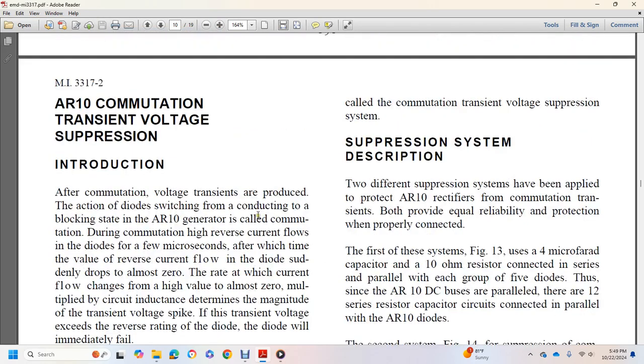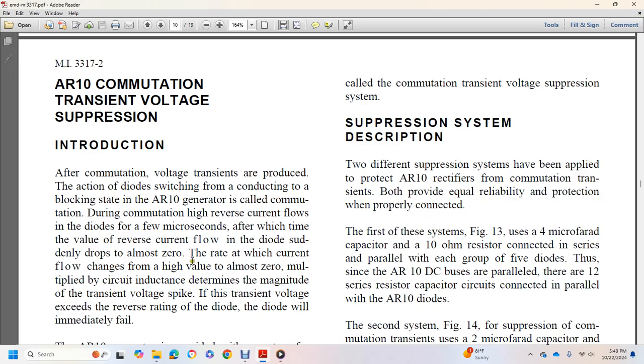Alright, AR10 commutation transient voltage suppression. Commutation is the voltage transition due to the action of the diodes switching between conducting and blocking in the AR10 generator. During commutation, a high reverse current flows in the diode for a few microseconds, after which the reverse current flow suddenly drops to almost zero. The rate at which the flow changes from a high value to almost zero, multiplied by the circuit inductance, determines the magnitude of the transition voltage spike. If the transition voltage exceeds the reverse rating of the diode, it will immediately fail.